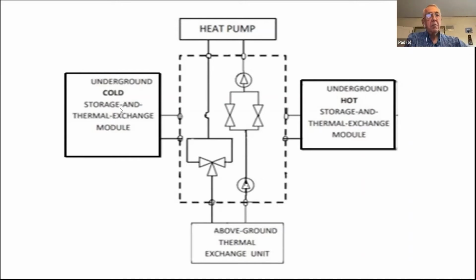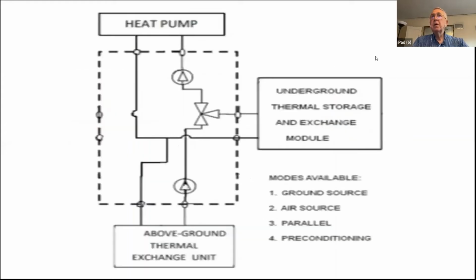Now, if it happens that somebody already has a ground loop installed for their building, let's say with a ground source heat pump, or if they absolutely have no way to get other than one ground loop, there's a way to handle that, and it becomes much simpler. And that's shown in this slide.